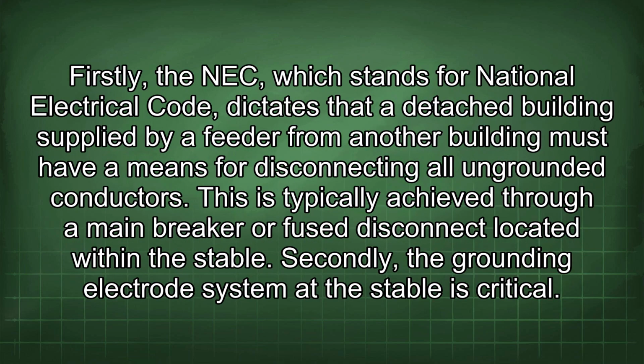Firstly, the NEC, which stands for National Electrical Code, dictates that a detached building supplied by a feeder from another building must have a means for disconnecting all ungrounded conductors. This is typically achieved through a main breaker or fuse disconnect located within the stable. Secondly, the grounding electrode system at the stable is critical.